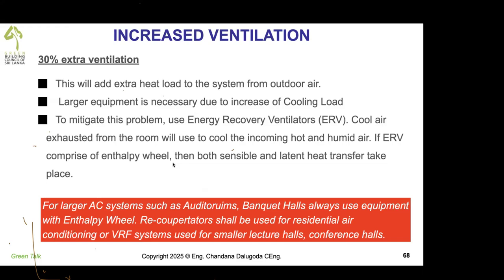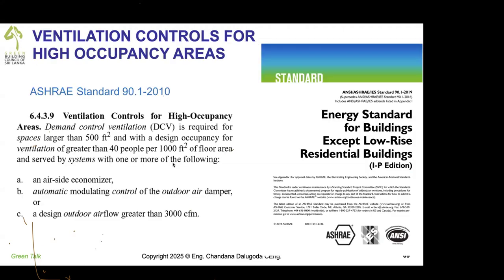Now, increase ventilation. There's another way of increasing well-being of occupants by increasing the ventilation air flow, but we calculated 62.1 method by 30%. That is, green buildings has to do that. But unfortunately, power consumption will go up because of the outdoor air quantity. Then we'll have to use energy recovery ventilators.